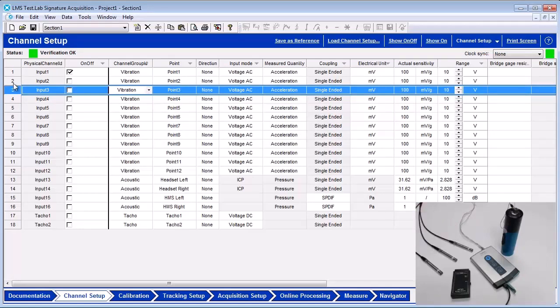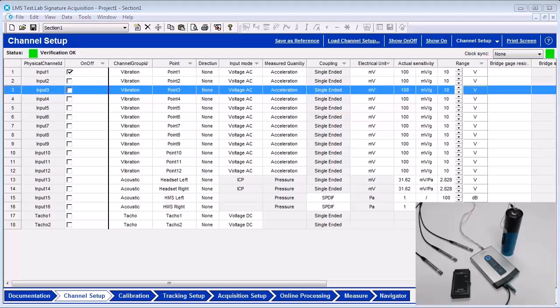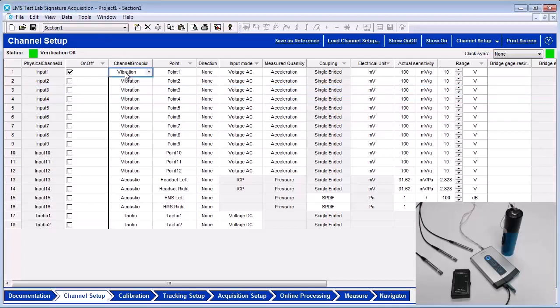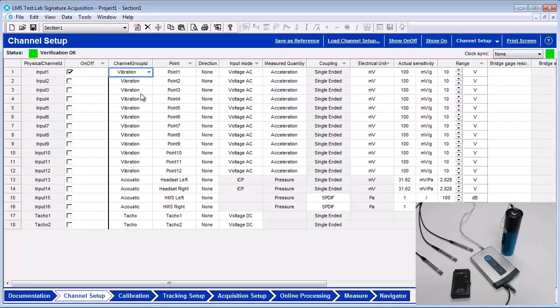In the channel setup, turn on the input 1 channel by checking the box next to the input name. Set the channel group ID to Acoustic. Set the input mode to ICP.